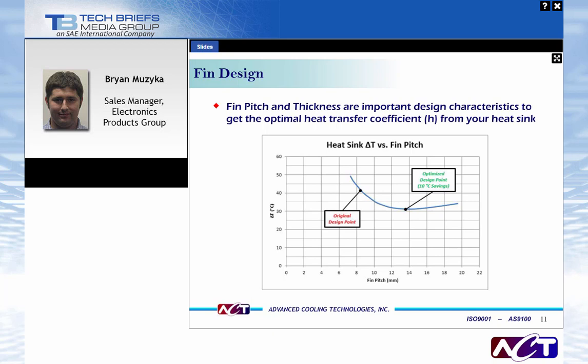This next slide shows how fin pitch and thickness are important design characteristics for optimal heat transfer performance. We took the original 8-millimeter fin pitch and optimized it. In natural convection settings, fins spaced farther apart reject heat better — if fins are too tightly packed, they tend to choke flow, causing large temperature rises. The optimal here was a little over 13 millimeters fin pitch. Using that instead of the 8-millimeter pitch gives about 10 degrees of savings — pretty significant just by sizing your fins correctly.